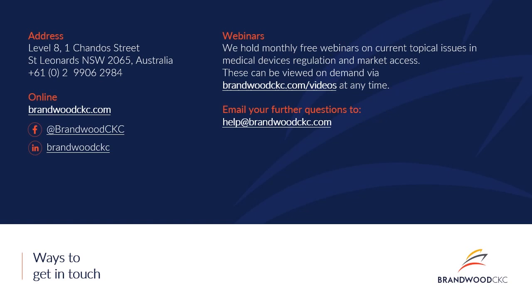However, I wanted to complete today's webinar answering a few of those. So question number 1, how often are CERs required to be updated? The key thing here is that a clinical evidence report is an active and evolving document. According to the MEDDEV, it should be updated if the manufacturer receives any new information from their post-market surveillance. If this has the potential to change the current evaluation, it should be immediately updated.